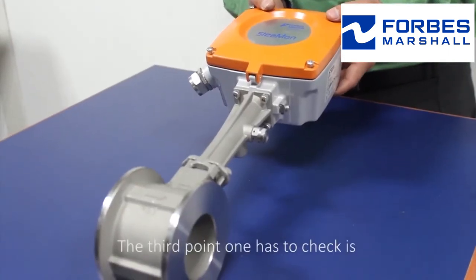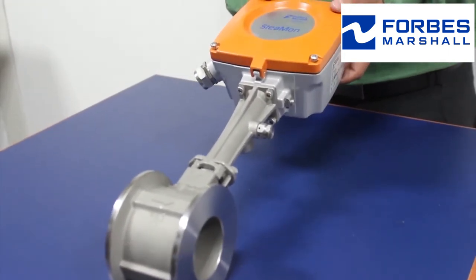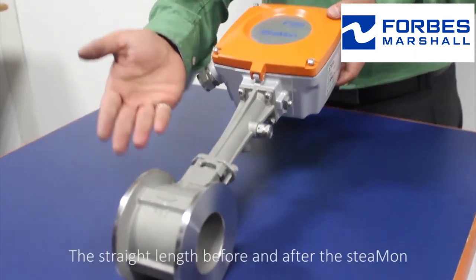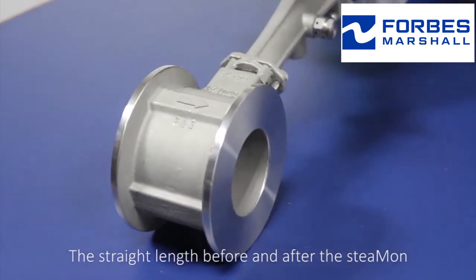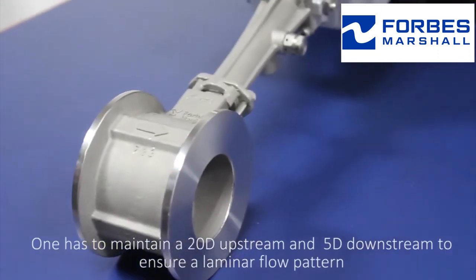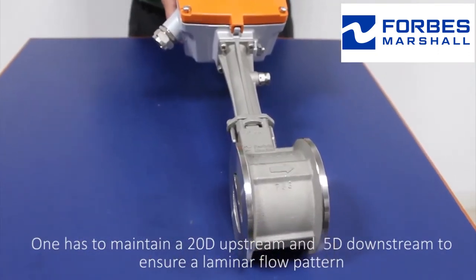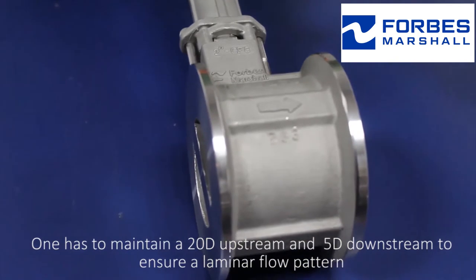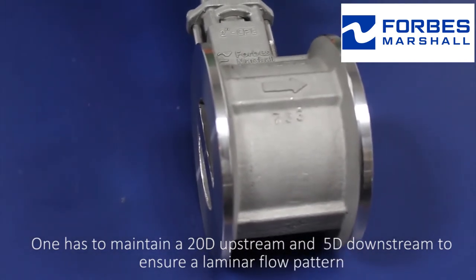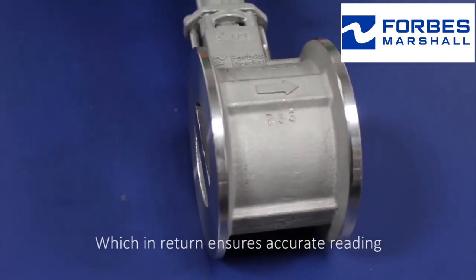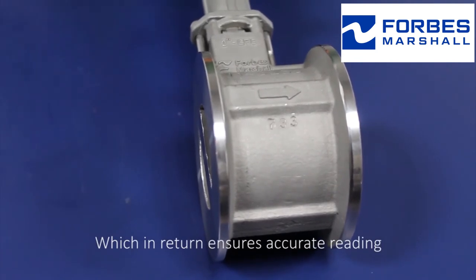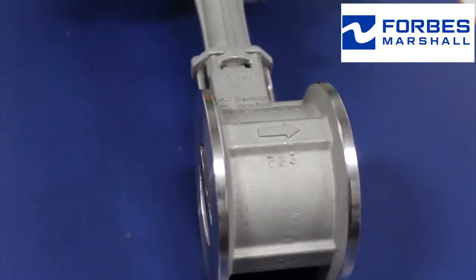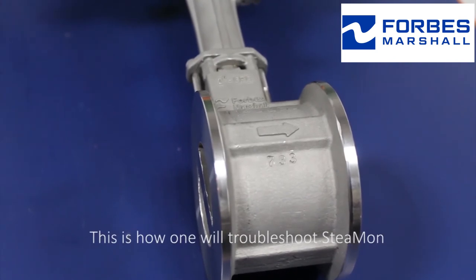The third point one has to check is the straight length before and after the SteaMon. One has to maintain a 20D upstream and 5D downstream to ensure a laminar flow pattern, which in return ensures accurate reading. This is how one troubleshoots SteaMon.